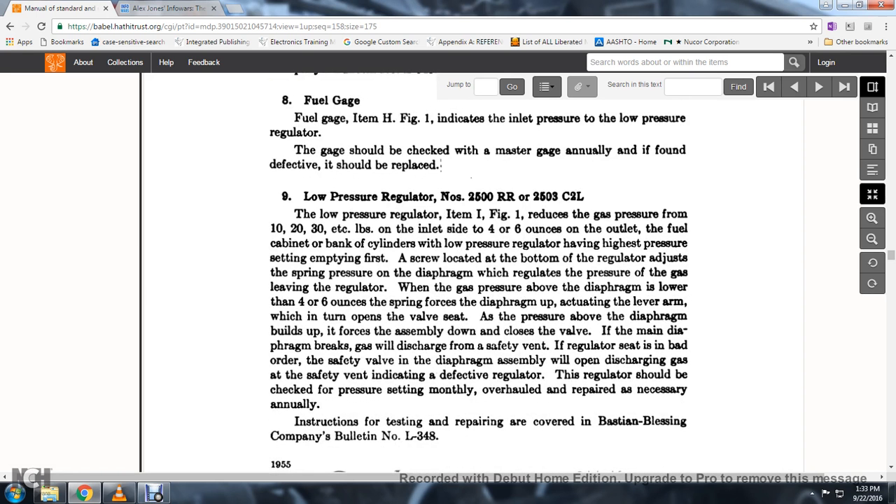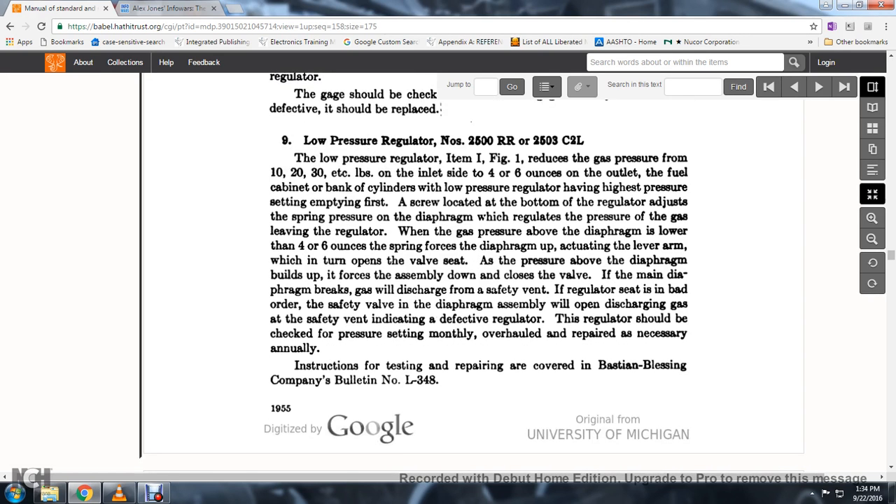Low-pressure regulator Nos. 2500RR or 2503C2L: this regulator, item I, figure 1, reduces the gas pressure from 10–30 pounds per square inch at the inlet to 4–6 ounces at the outlet of the fuel cabinet bank. Cylinders with a low pressure regulator have the high pressure on the setting. The adjusting screw at the bottom of the regulator adjusts the spring pressure of the diaphragm to regulate the pressure of gas leaving the regulator. If the diaphragm breaks, it will discharge from the center safety vent; when the regulator is in bad order, the safety valve and diaphragm assembly will open and discharge gas through the safety vent, indicating a defective regulator. The regulator should be checked for pressure setting monthly and overhauled or repaired annually.